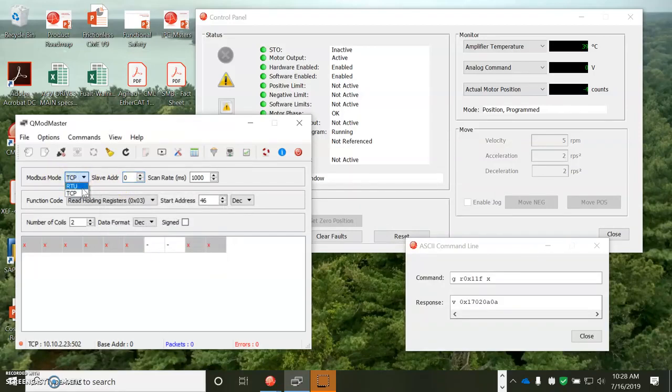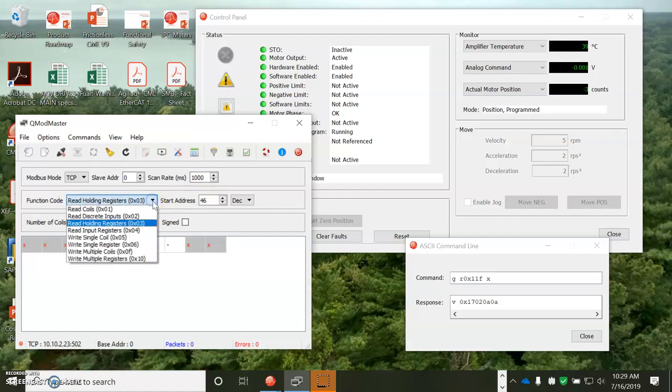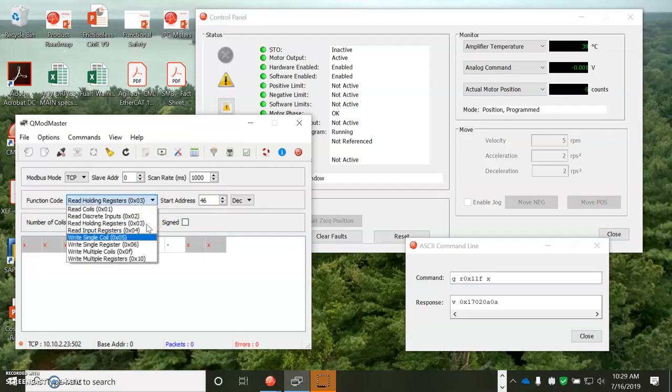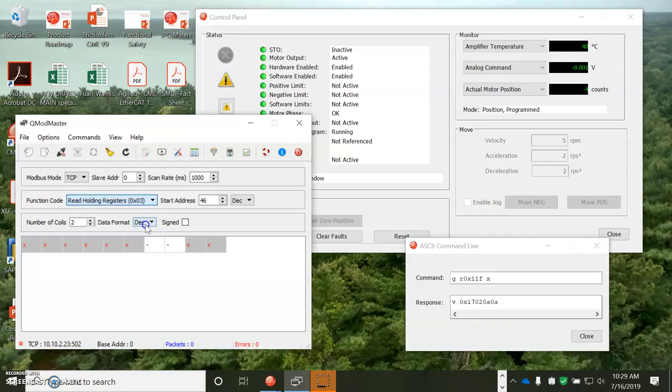We're going to do not RTU but TCP. Slave address, single-axis drive, 0. If it was a three-axis drive, I could talk to 0, 1, 2. There's a scan rate. These are the function codes. I'm going to read the holding register. I could write to the holding registers. Hex 10 is 16, so function 16.